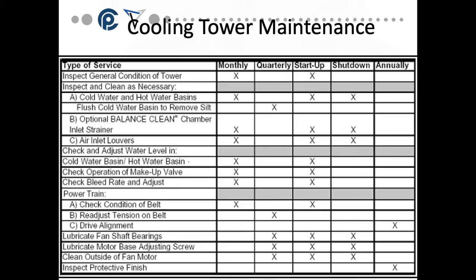Okay, so when we look at this maintenance chart, this is something that you'd get from the manufacturer. Monthly, they're suggesting you inspect general condition. It's suggesting you inspect and clean the cold and hot water basins. They're suggesting the inlet strainers and air louvers get cleaned. So if you take a look at a maintenance schedule, it basically outlines what you're going to do from a maintenance perspective on a monthly, quarterly, startup, shutdown, or annual basis.